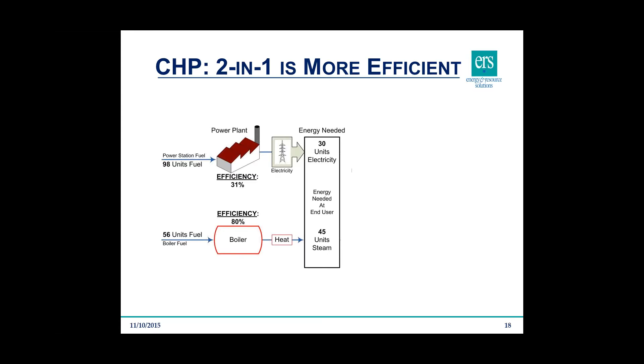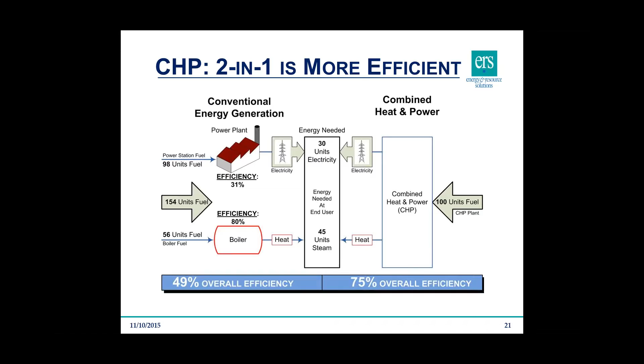At the same time, the 45 units of steam I would produce on site in a mechanical room with a boiler. Those are typically about 80% efficient, so I need 56 units of fuel to produce my 45 units of steam. So all told, we're using 154 units of fuel to produce my 75 units of electricity and steam, which leads to a 49% overall efficiency. Now with the CHP system, on the other hand, I put in some fuel, and at the same time I'm producing both electricity and thermal needs. With CHP systems, we typically see an overall efficiency of about 75%. So 100 units of fuel to meet my 75 units of need. On a system-wide level, we're using significantly less fuel to meet the same demand.